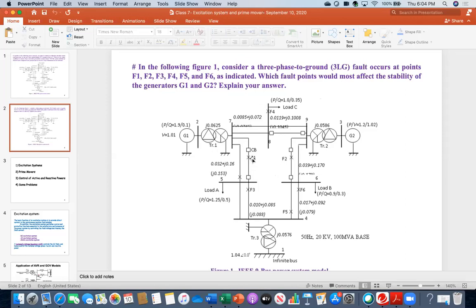The closer the fault location, the level of severity will increase. Because the distance from here to here is different, and with the increase of distance, impedance increases. If impedance increases, then your current flow will definitely decrease.